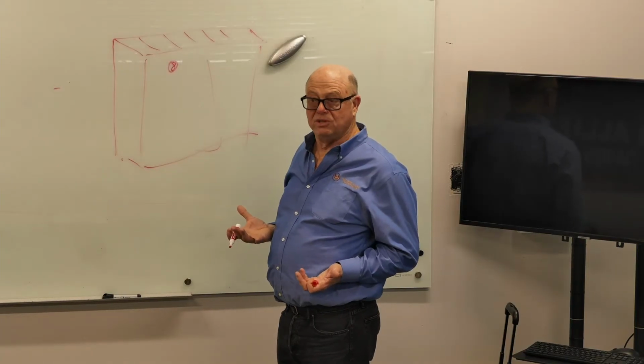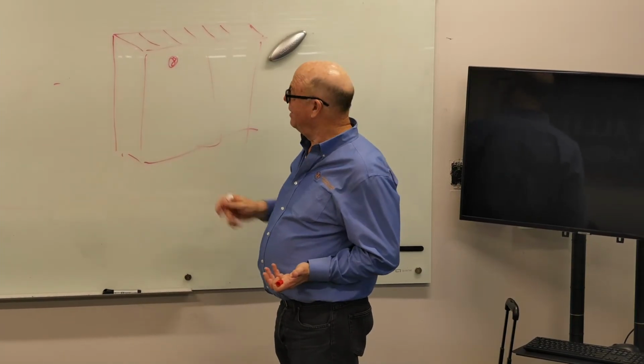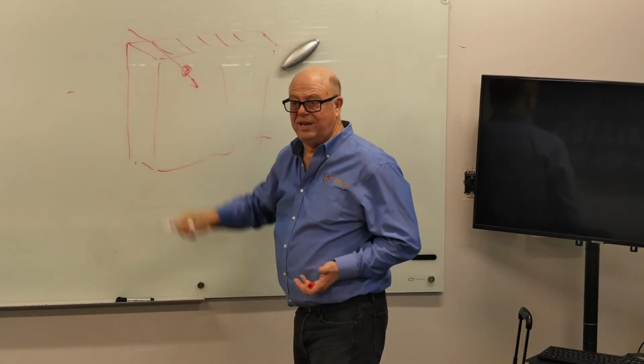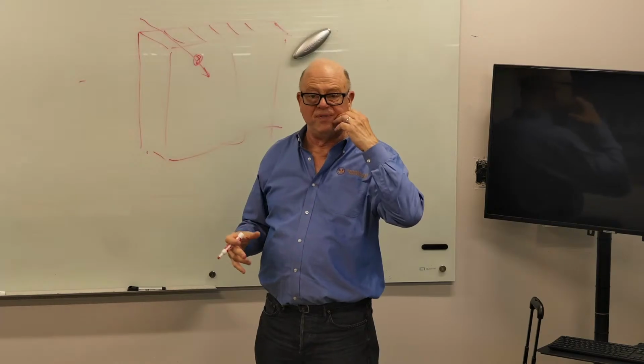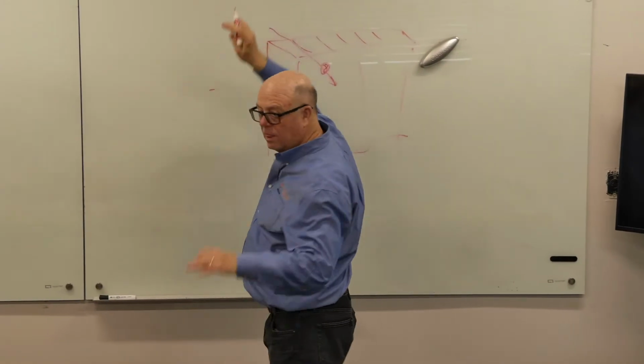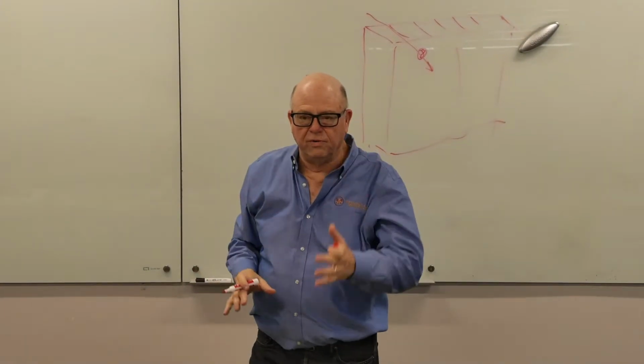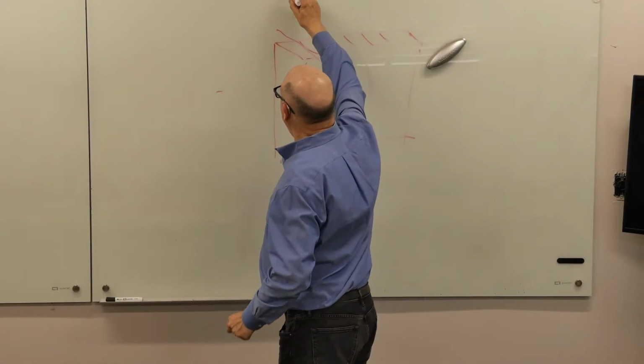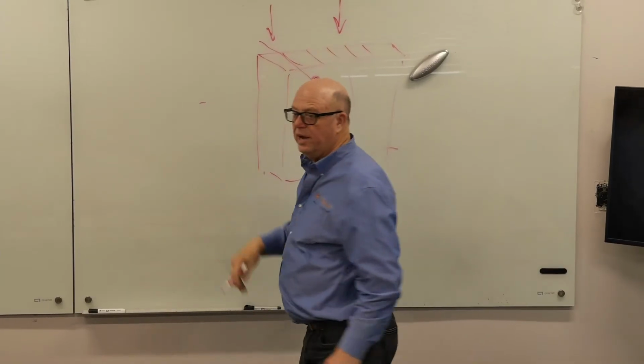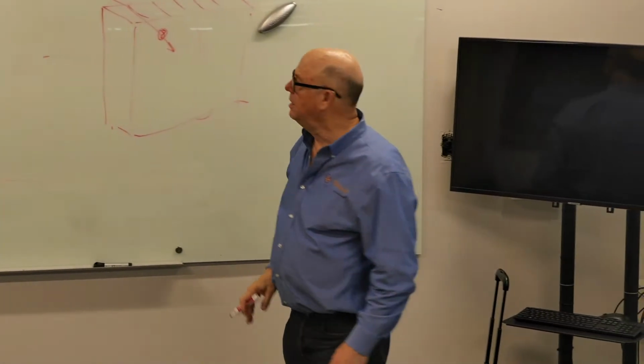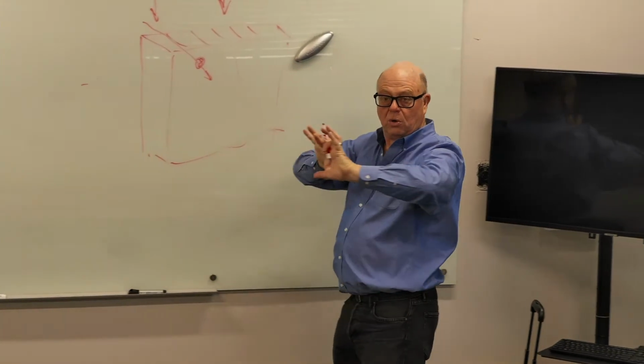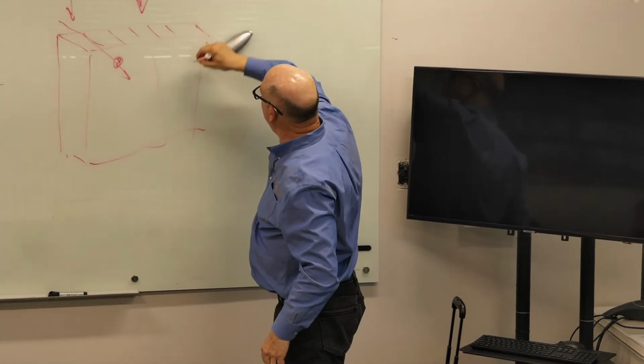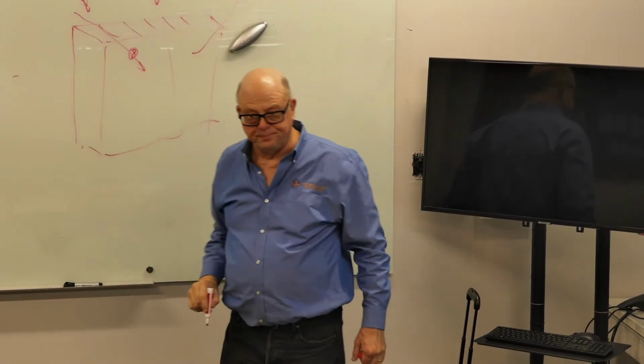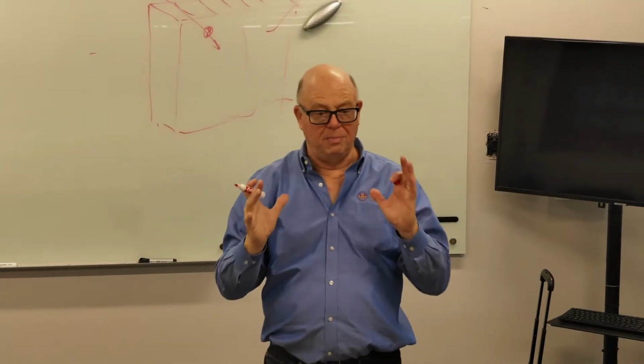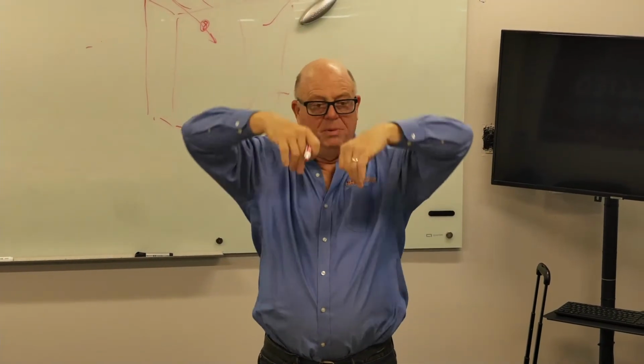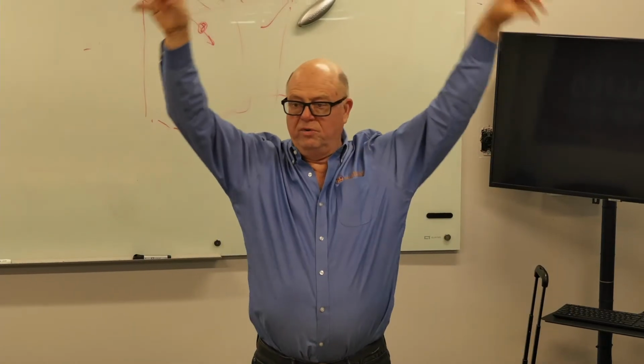Hot aisle. And why am I standing in the hot aisle? Because the air's going this way, right? And it gets heated up. And I'm standing there and it's blowing in my face. Now we're talking server rooms 30 years ago. What you would do is you would put the cold air in on this side, the cold aisle, and then the little muffin fans would be drawing the cold air through, and then you'd put the return on that side. And if you had two, you probably were putting the cold into the middle, and you had them pointed, and you took the return from both ends.